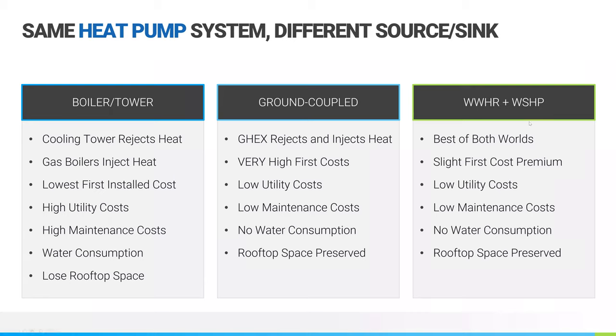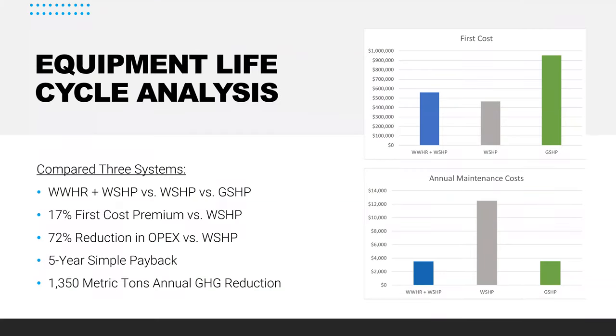So what that did is the wastewater heat recovery system really gave them the best of both worlds. It was about a 17% cost premium over the water source system, and still provided the same low utility costs and low maintenance costs and freshwater consumption preservation that you got from the ground coupled system as well. So we were really looking at that life cycle analysis, and again, it was 17% more than the water source, but in your operating expenses, it was a 72% reduction. So when we're talking operating expenses, we're not just talking utility. That's your maintenance and your upkeep and everything that goes into operating that piece of equipment. So this is where they really got that sense that the wastewater heat recovery system was going to provide the best payback for them. And they were actually calculating a rough 5-year simple payback for the entire system. And at the same time, we're able to eliminate 1,350 metric tons annually of GHG emissions on site.